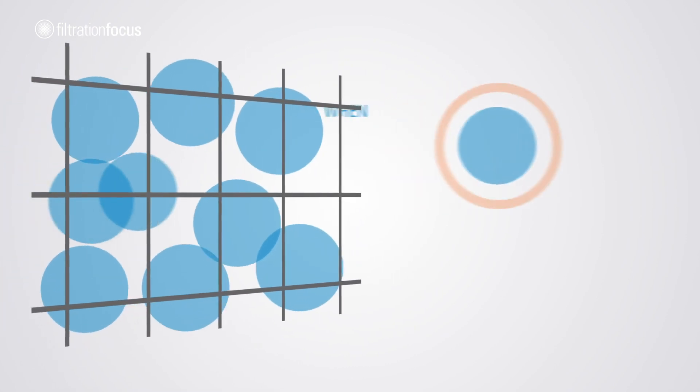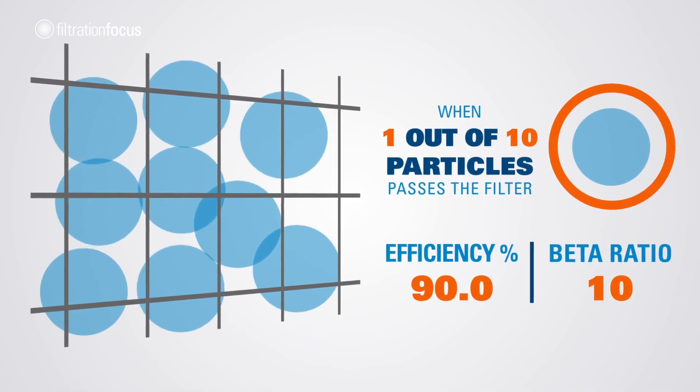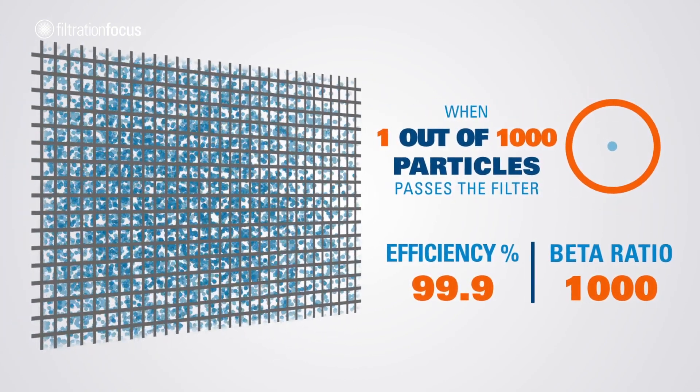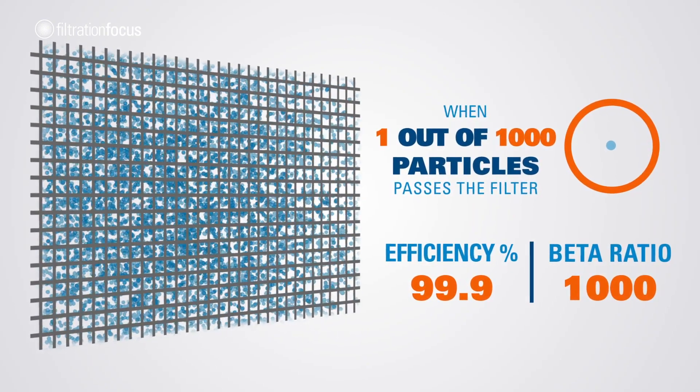For example, at a specified micron size, when 1 out of 10 particles passes the filter, it has an efficiency of 90% or a beta ratio of 10. When 1 out of 1000 particles passes the filter, it has an efficiency of 99.9% or a beta ratio of 1000.